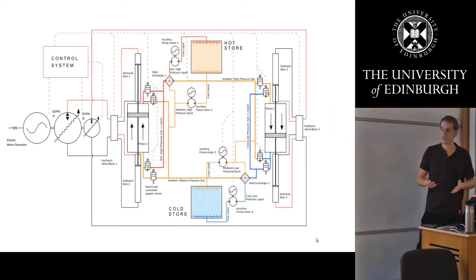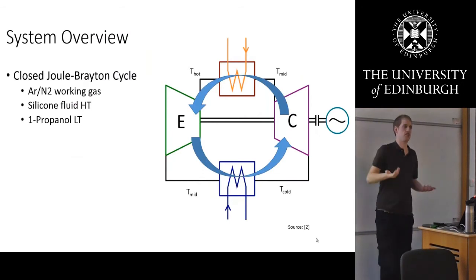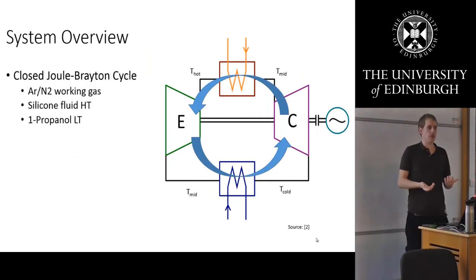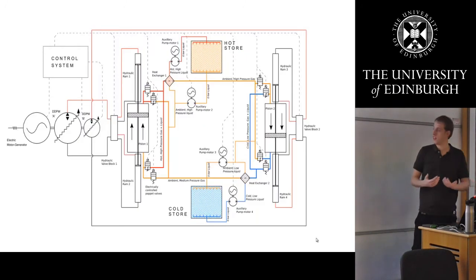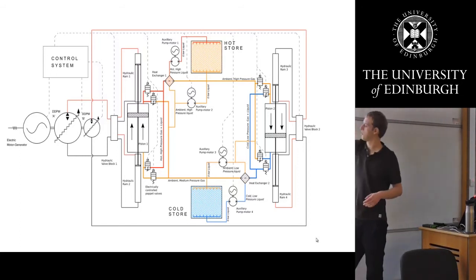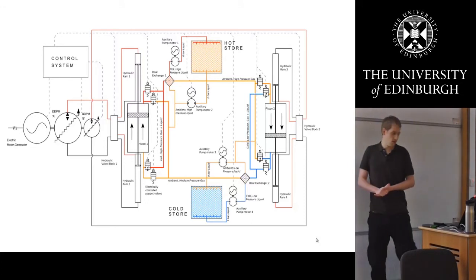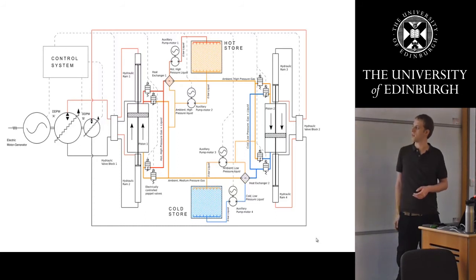So what it looks like in practice is a lot more complicated. These are, like, this would be turbo machinery type things. You might see it in a steam turbine or something. What we found is that the efficiency for these type of turbines just wasn't where we needed them to be. So the working concept now is, maybe it looks a bit Victorian to some people, but essentially it's a large piston compressor. And the reason for that is we really need to keep the efficiency quite high on this to get that 70% round-trip efficiency number. So this is a working concept. You can see we still have the hot and cold stores there. You've got your compressor and expander here, and there's some heat exchangers involved. So the grid basically comes in right here from your electric motor generator. It drives some very controllable hydraulics, which then drive these piston compressors back and forth.